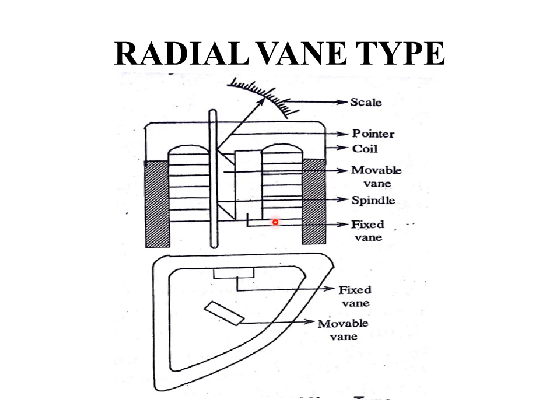This is the construction of a radial vane repulsion type moving iron instrument. It consists of a coil and two vanes: one movable vane and one fixed vane. The fixed vane is attached to the coil, whereas the movable vane is mounted on the spindle. The spindle carries the pointer which moves on the graduated scale. If the vanes are radial, it is called a radial vane repulsion type instrument.